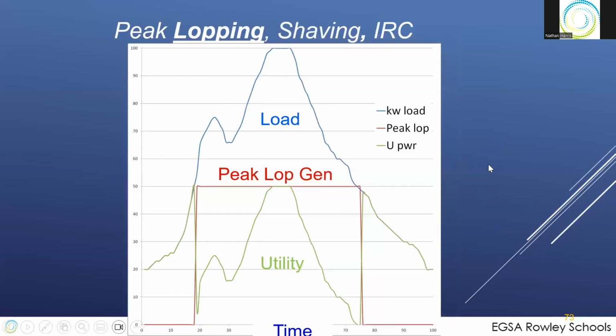Peak lopping was developed by some other controller friends of ours, and their term is somewhat similar. Instead of the actual value of watts being purchased from the utility, they only need to know that the load has reached a certain level of watts. So when the load reaches a certain level, in this case 50, we send a start signal to the generator to run in parallel with the utility. And as long as the load's above 50, we run the generator in parallel. When the load drops below 50, we turn the generator back off again.